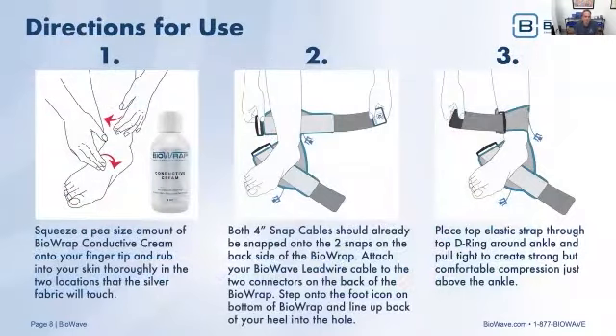So let's talk about some of the pro tips for applying this device. It's important to take you through this to make sure that your patient is going to get optimal results from using it. First and foremost, in order to allow our devices to deliver the high frequency nerve stimulation through these much larger electrode areas, we have to place a conductive cream, just a pea-size amount for each of the electrodes, rubbed into the skin. So you have to rub it in completely around the entire region just proximal to the ankle and completely around the tarsal and metatarsal area of the foot.